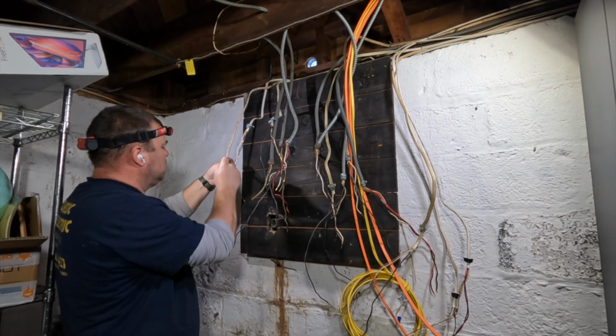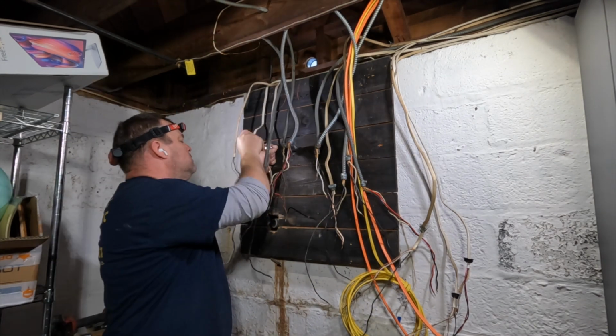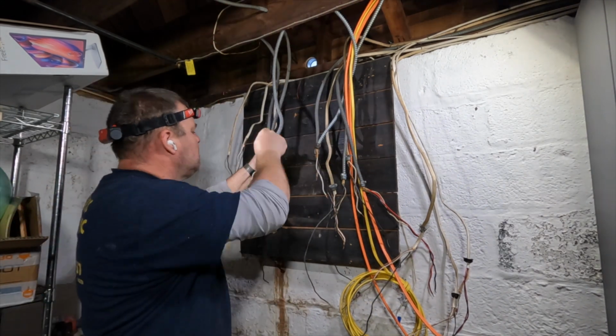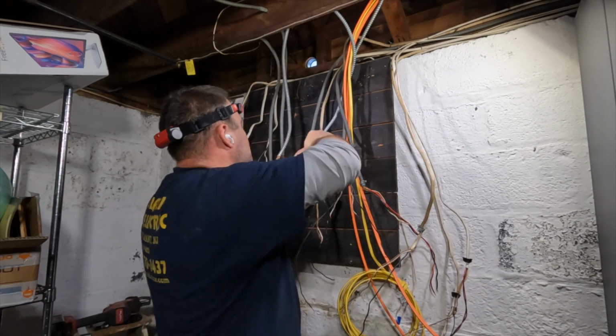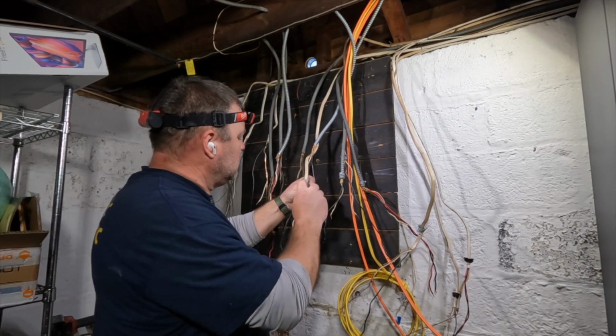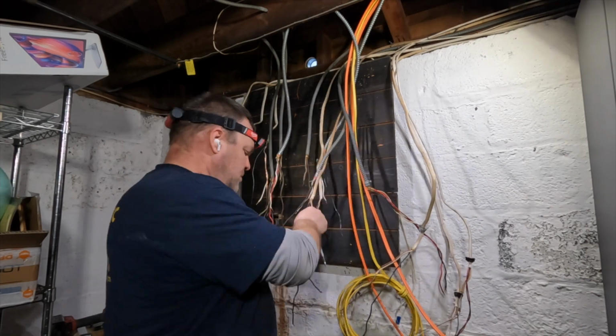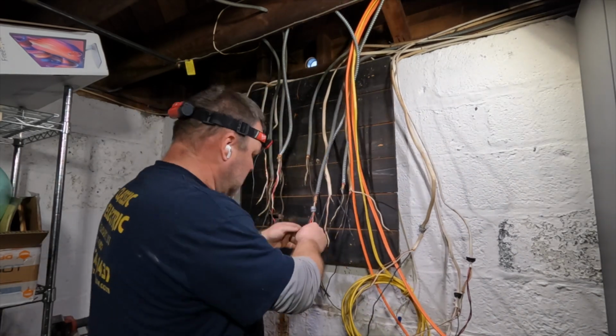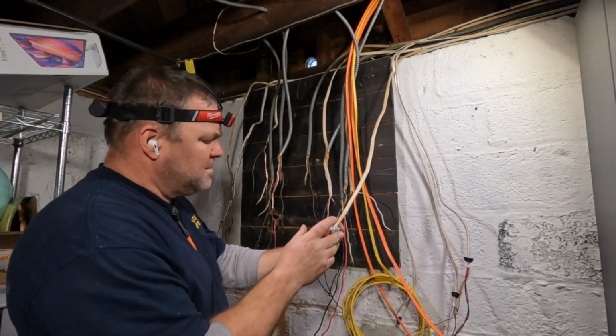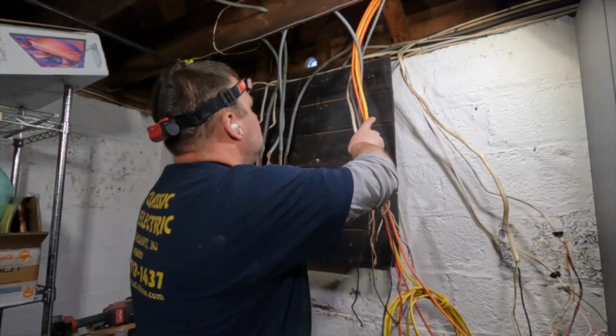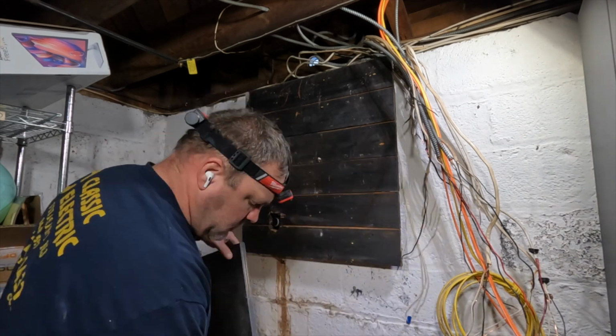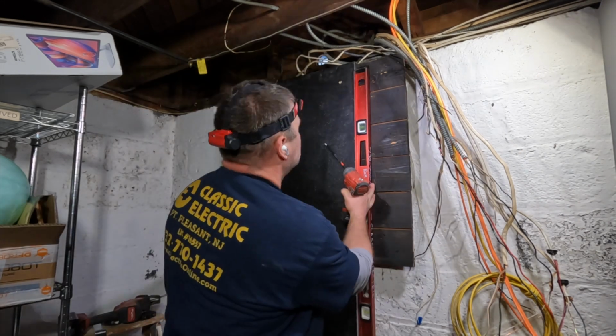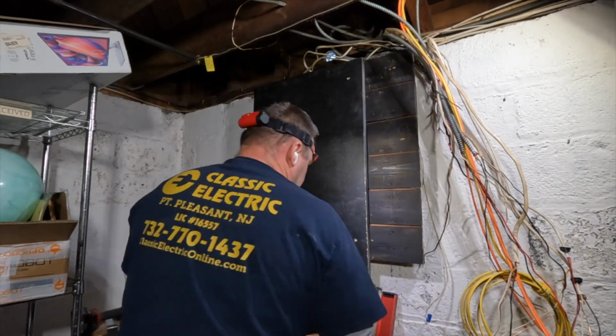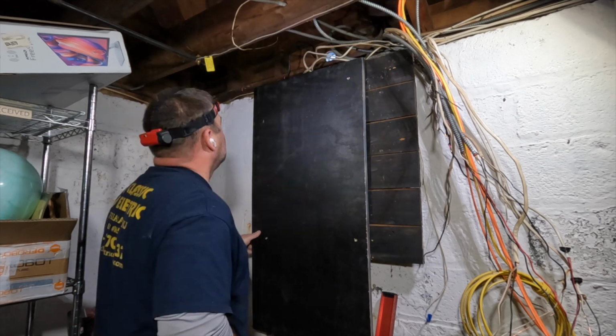this. So as you can see, this mounting board right here, I tugged on it a bunch of times and it did not move. It did not budge at all. So I decided to leave it in place and to add my 2x4, not my 2x4, my 3/4 inch plywood mounting board, and mount it directly to this old board that's here. I'm taking off all of the old connectors so that we can properly trim back the sheathing or the armored cable sheathing, so that all these conductors can come right into the top of the panel in a neat workmanlike manner. The NEC actually does address neat workmanlike manner in article or section 110.12, the execution of work.